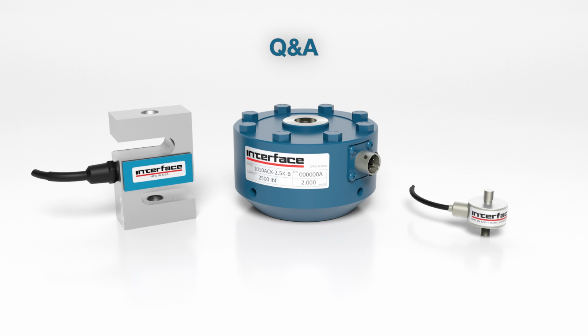Can someone elaborate on how the load cell cable placement can influence the measurement? Well, anytime the cable of the load cell has the ability to impact the force exerted on the load cell, it's going to have an effect on the measurement. Again, that's one of the talking points on the SM load cell, that we want to make sure that cable is not somehow exerting a force into the load cell or influencing the deflection in some way. You can imagine as you're cycling the load cell up and down and the cable's dragging or hanging on something, it does become a parasitic load path. So again, we want to minimize any impact that the cable could have.